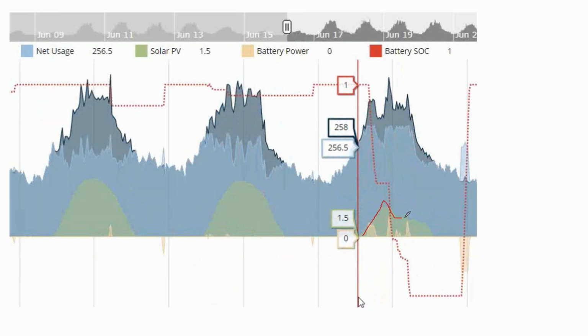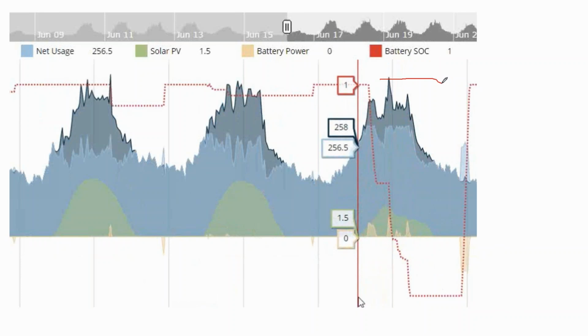But on partly cloudy days, we still get the same facility demand as on full sun days, except now one cloud sits on top of our solar array right during peak times. If our solar array turns off, our demand charge would be exactly what it was before, because our array is off for a 15-minute window. These commercial demand rate structures aren't based on maximum demand every day, just the maximum demand for a 15-minute sliver.